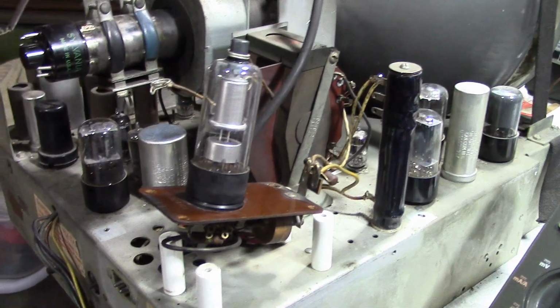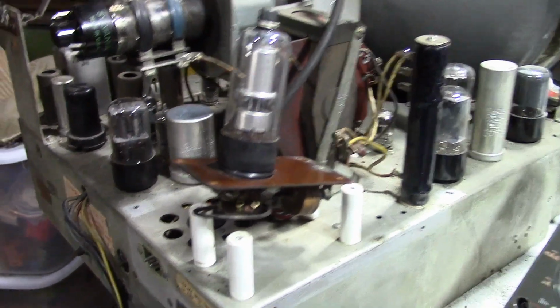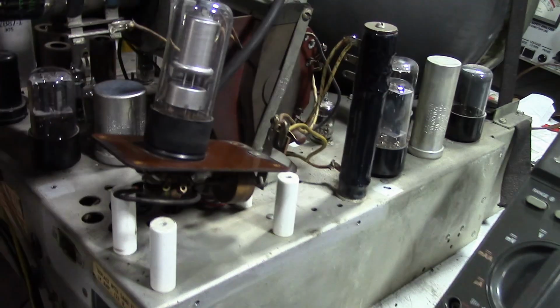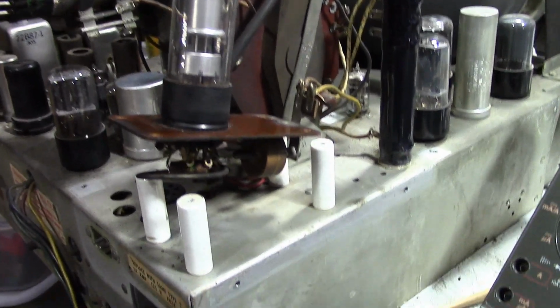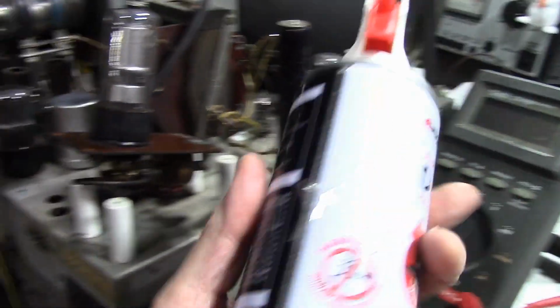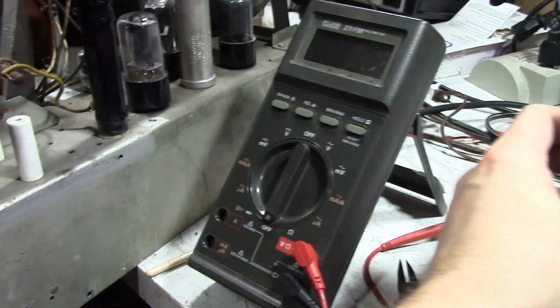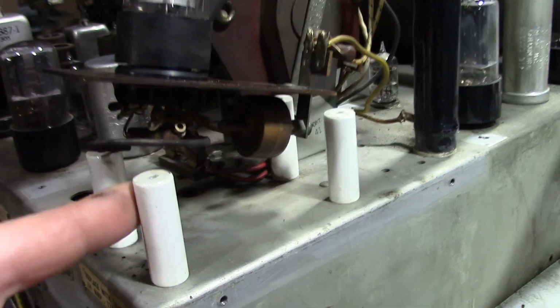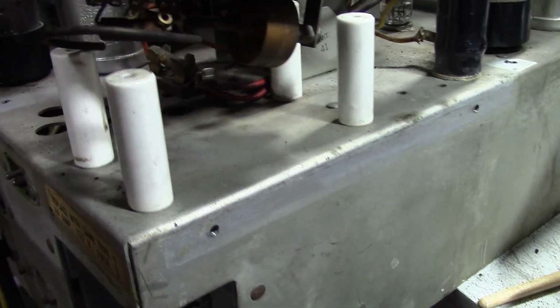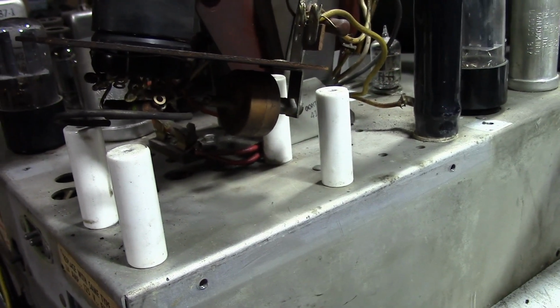Here's a look inside the high voltage box. I just had to remove a few sheet metal screws and it lifts off. I blew out the dust with some compressed air and used some Spray 9 multi-purpose cleaner to clean off these ceramic insulating mounts. Whatever was on them seemed to really be caked on, so I had to use some Q-tips and that Spray 9 to get it off.